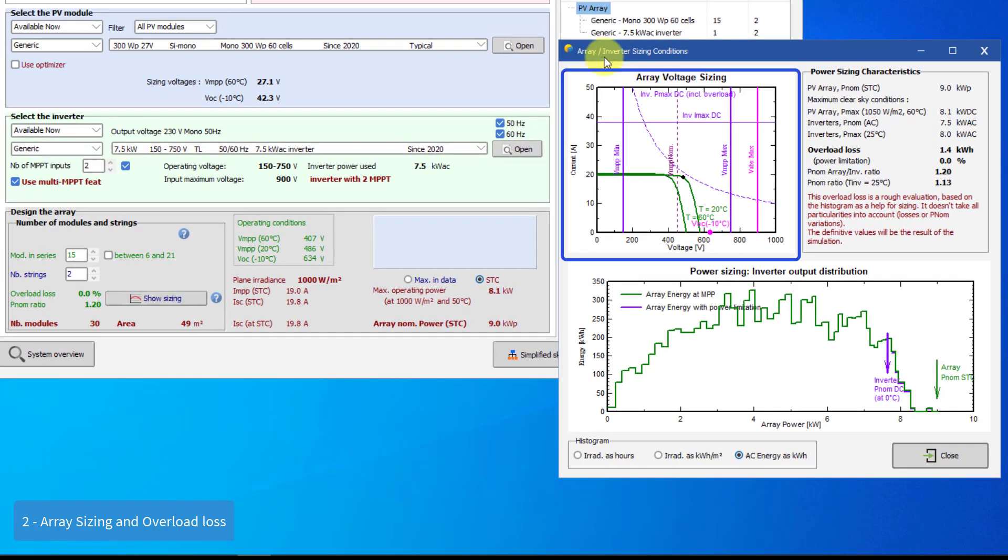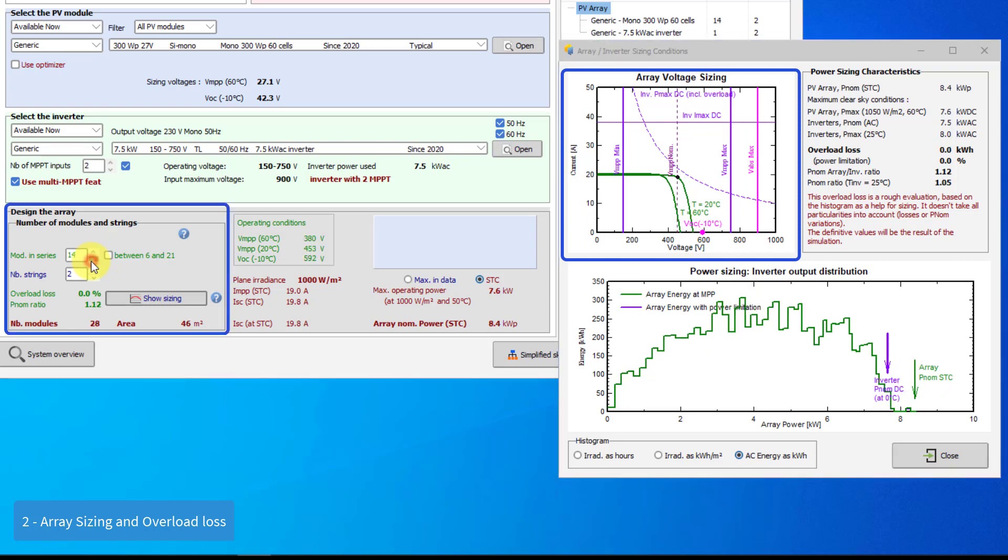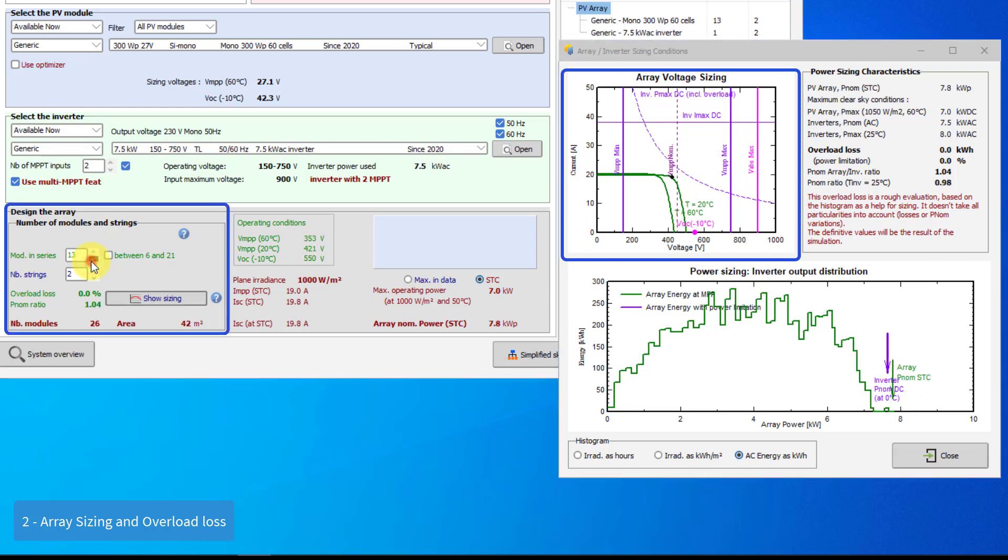A first graph shows the voltage constraints, which will determine the number of modules in series. Here you have the PV array IV curves for winter conditions, i.e. the high voltages, and for the summer conditions, i.e. low voltages. The graph shows the lower and higher voltage limits of the maximum power point tracking, or MPPT. The MPP values of the IV curves should lie between these limits. You see also the maximum open circuit voltage at lower temperatures. This should never exceed the absolute maximum voltage allowed for this inverter.